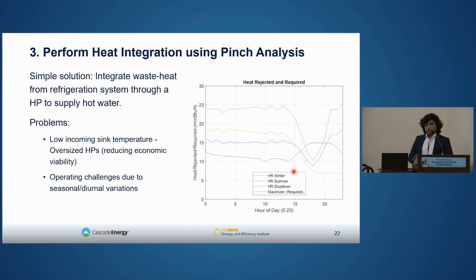Next step was to see their heating and cooling loads and identify any heat reclaim, heat exchange, or heat pump opportunities at the facility. And for this, on the right, this chart shows their heating demand and the heat they're rejecting at every hour of the day. So the purple line at the bottom is their heating demand for hot water, whereas the blue, the yellow, and the red are heat that they're rejecting from the refrigeration system. Each of those lines is a different operating scenario.